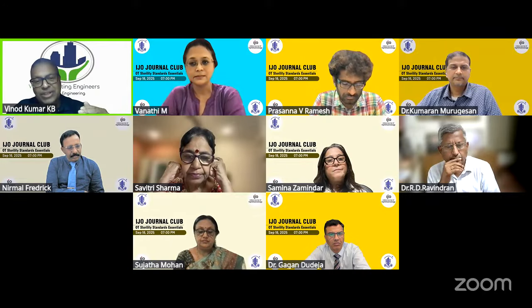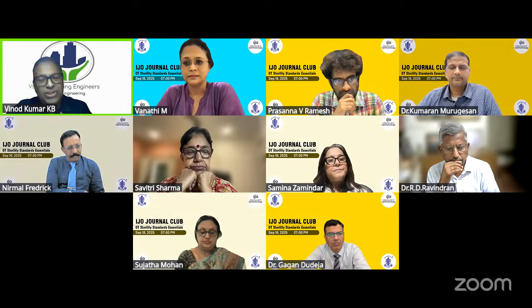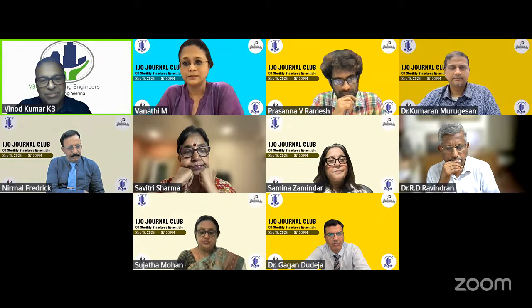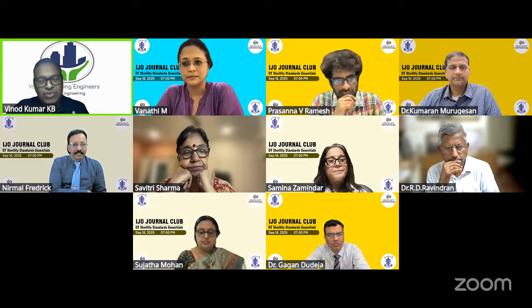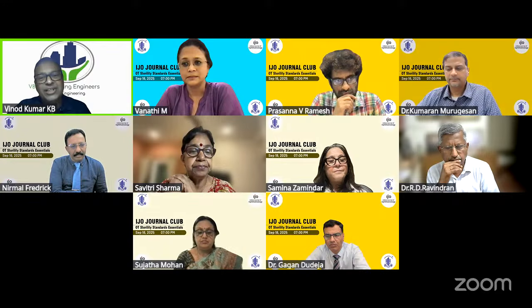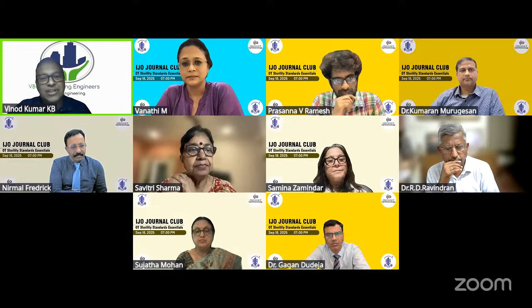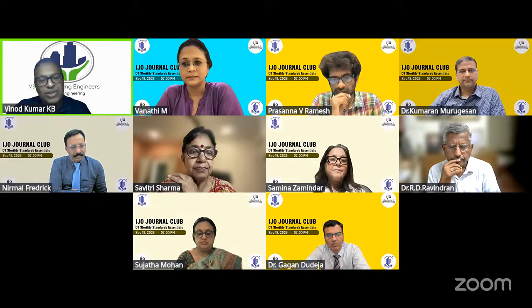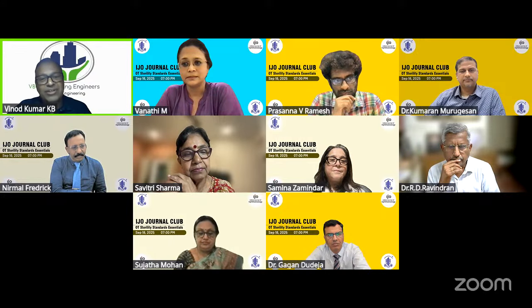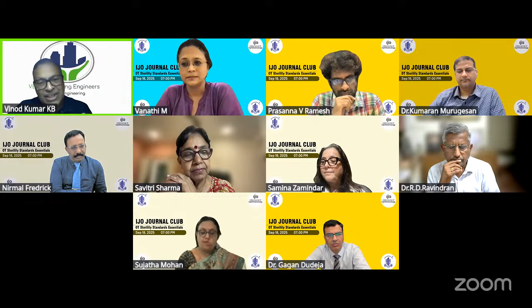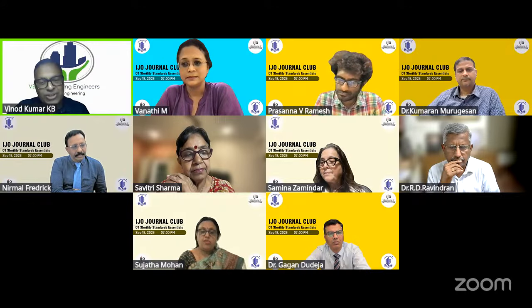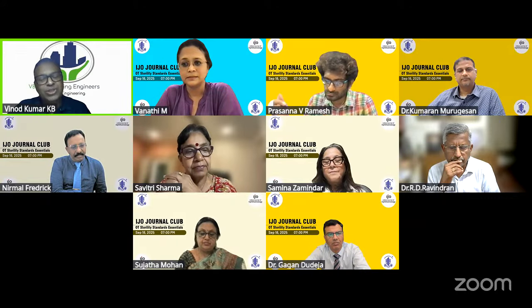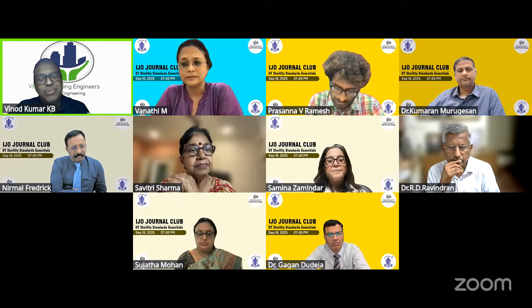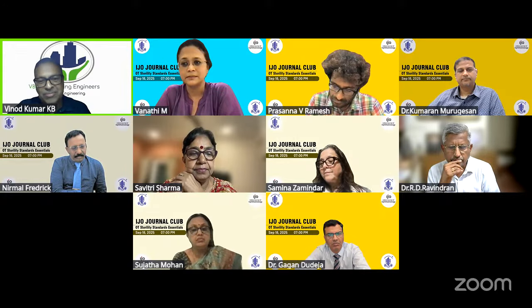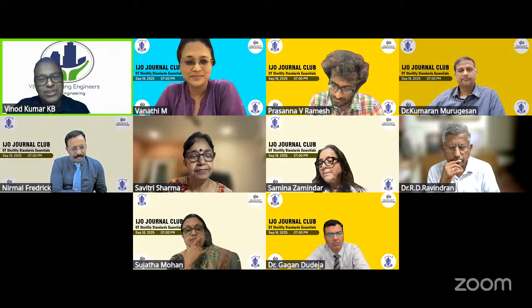Coming to 50 to 55%, my question has always been this: if I sit in front of the operation theater room, you can imagine the number of times the door is being opened, the number of times infiltration and ingress of air is going to happen. And now across India, it's rainy season. You can imagine the level of humidity in the sterile corridor itself, forget the semi-sterile. This sterile corridor is going to bring humidity into the theater. Now, the AHU has a high static fan, whereas a split AC has a low static fan. A high static fan can push the air through all the filters. A low static fan like a split AC can only handle 10 micron filters, but an AHU can handle up to 0.3 micron filters. That high static pressure also gives you positive pressure in the room, which reduces the ingress of air and of humidity.